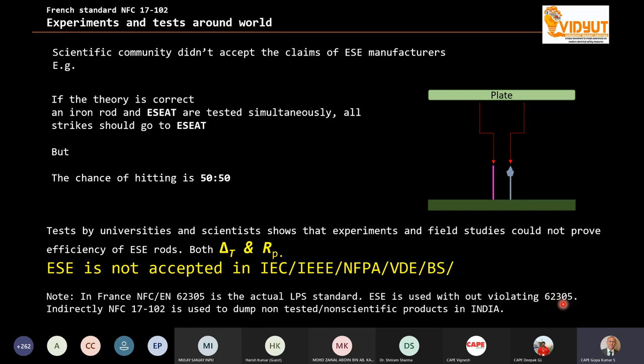Coexist in the sense that you have a very good guard, which is the 62305, the norm, the conventional lightning protection as per the IEC standard. In addition to the protection, they make one more rod. That means the word which they say is coexist. ESE is coexisting with the IEC lightning protection system. What they say is you make a lightning protection as per the 62305 standard, and then you put an ESE in addition. Of course, if you have money, you can do that.